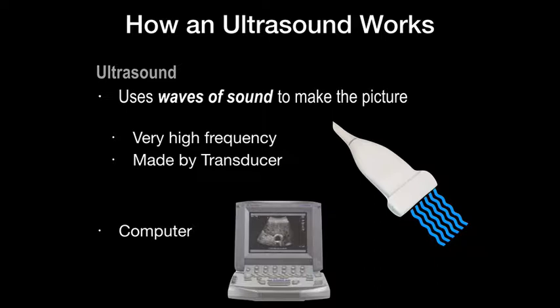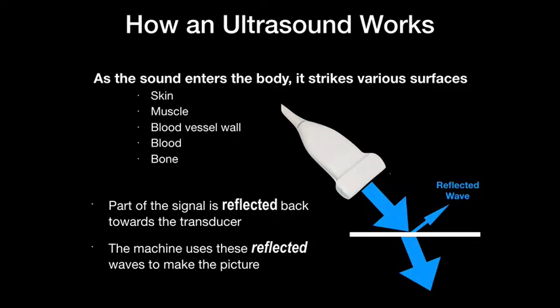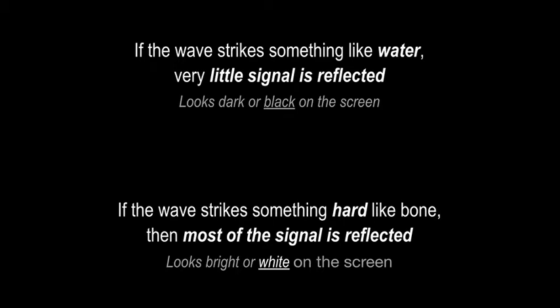The transducer is also very fragile — essentially made of glass — so if you drop it, it will break. As the sound wave enters the body, it strikes interfaces — changes in density — which could be the skin, muscle, fascia, blood vessel wall, or blood itself. Every time it hits a different density, it sends back some of the sound waves as a reflected wave, and that's what the ultrasound uses to make pictures. The transmitted wave continues deeper into the body to image deeper structures.